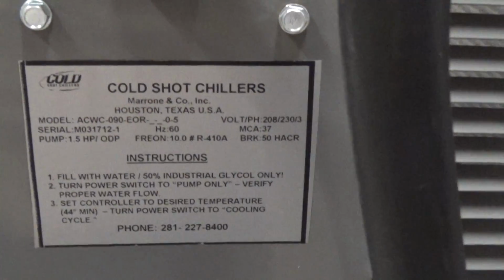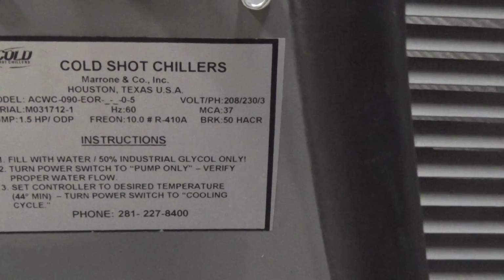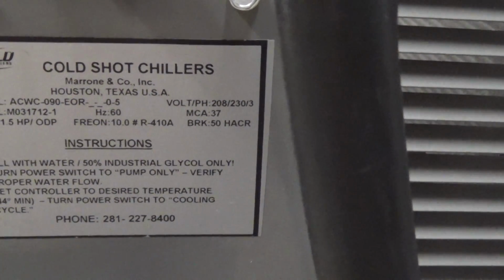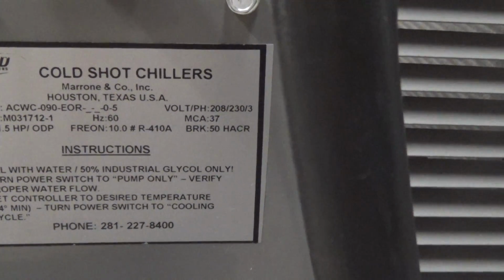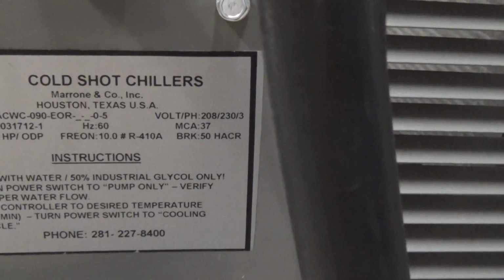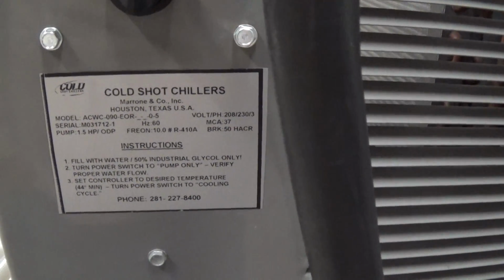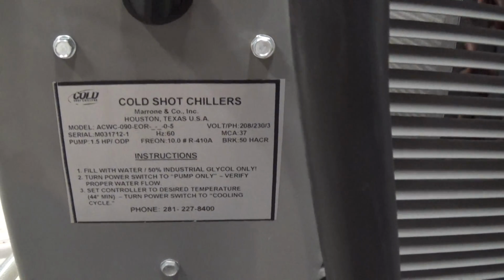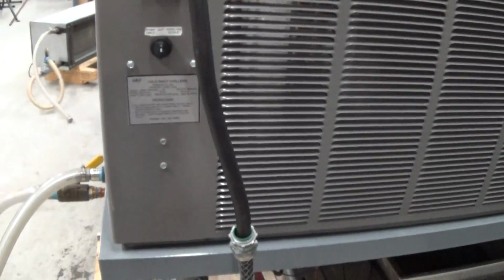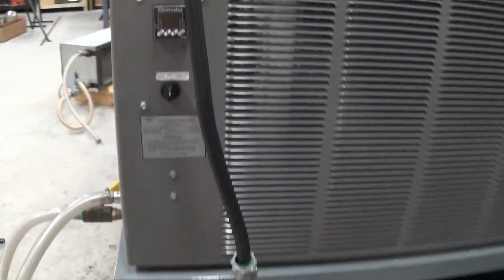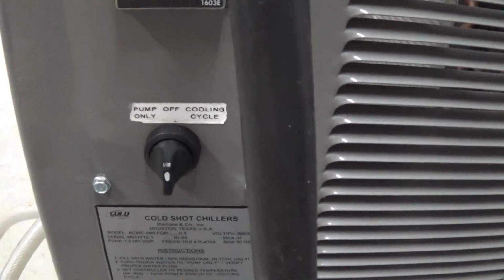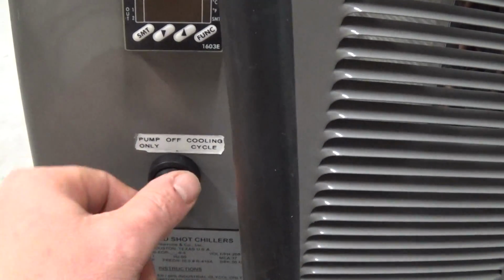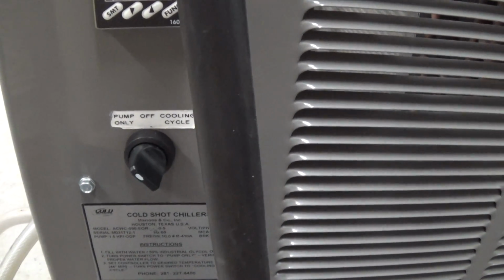They call it the ACWC-90, serial number M031712-1. It's a 2012 with the newest R410a refrigerant and a 1.5 horsepower process pump. We're just going to go ahead, and we have power to the unit here, and we're just going to turn on pump. And when you first start up the unit and power it up, it is phase dependent.